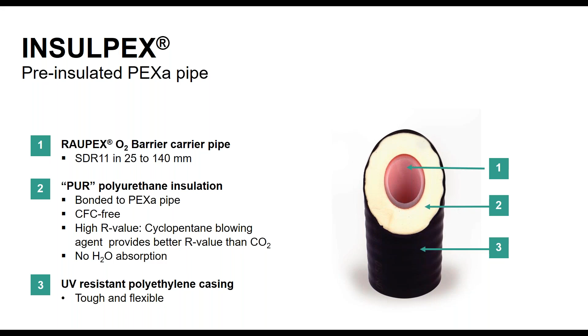And then the jacket — as far as putting it outside, UV resistance is important too, because a lot of these projects are going to be uncovered for a while. So it's nice that it's not directly on the carrier pipe, which is why in the PEX industry as a whole we put different types of coatings and jackets on the pipe to keep the sun off it. So you're in good shape with the extra jacket on this product as well.